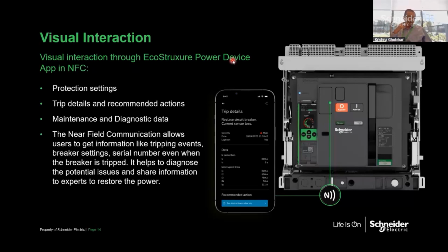One more feature which we have brought, particularly for MTZ Active to start with, is, today some projects are asking for a total coordination or a discrimination between a breaker and a downstream circuit breaker. Of course, we have the charts called the complementary technical guide with all the permutation combinations of incoming or outgoing, like ACBs, MCCBs, MCBs, and so on. Now, in EPC, we are bringing a new functionality where you can test this. So it's not only via a table or via a certificate to say that this discrimination is there. We can also do testing with the EPC.